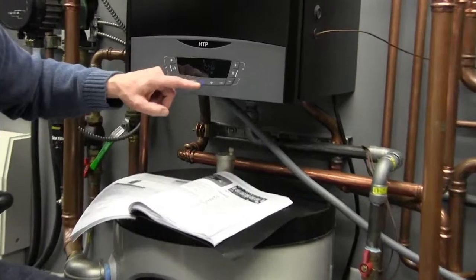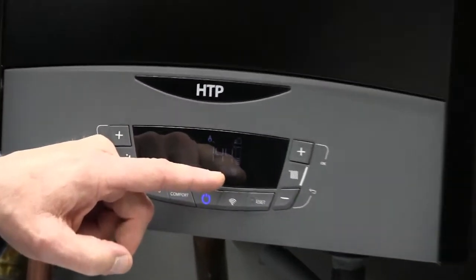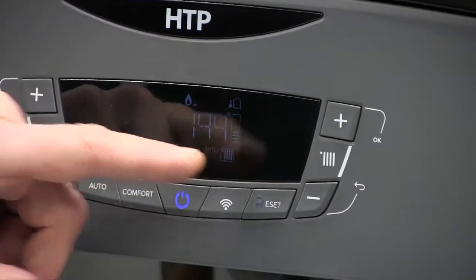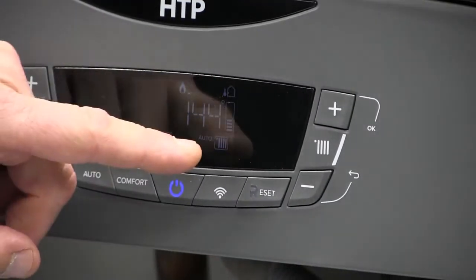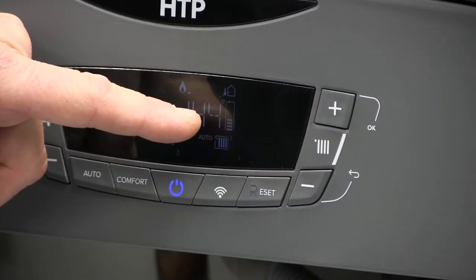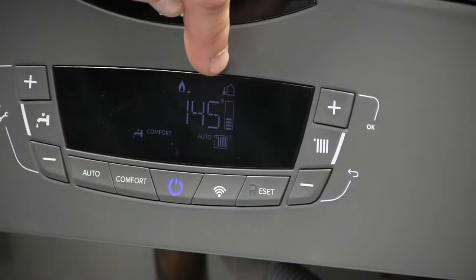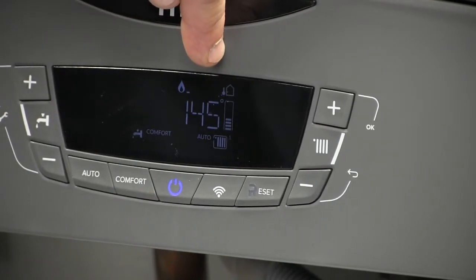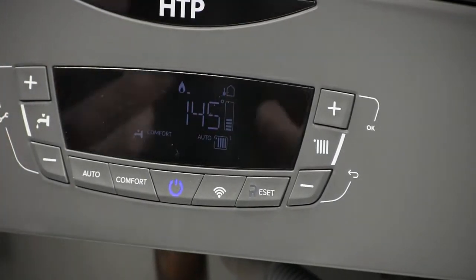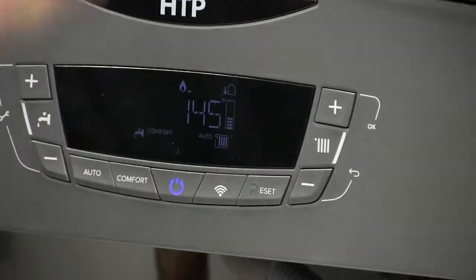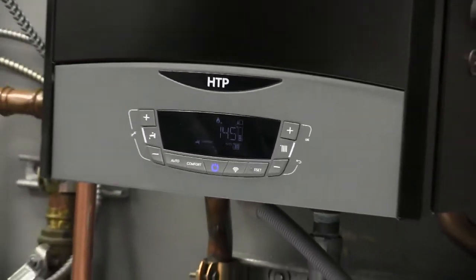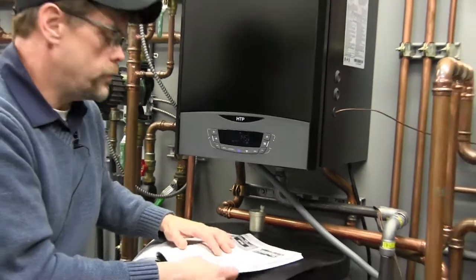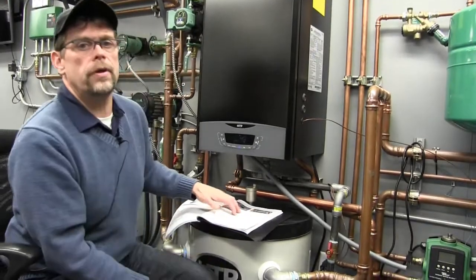We're in outdoor reset strategy. There is a central heat call on zone 1. We're about halfway on our temperature to our set point in that we are utilizing an outdoor reset strategy. So that's a quick synopsis and lets me know what the boiler is doing at the moment. So good thing to review. Again, that would be found on page 59.